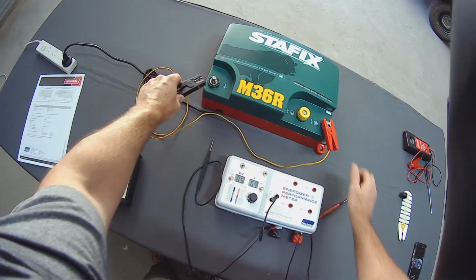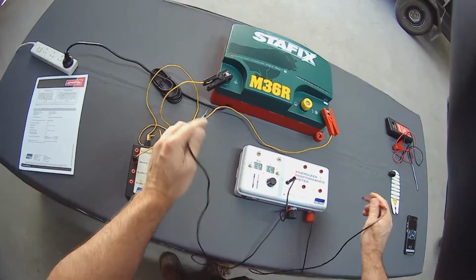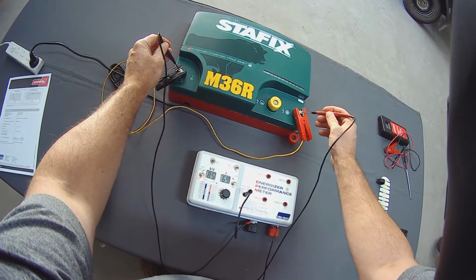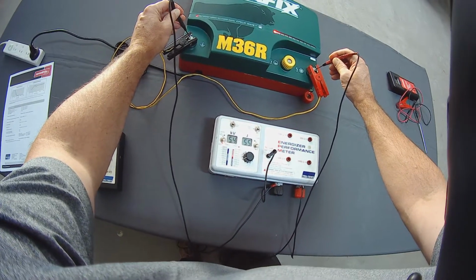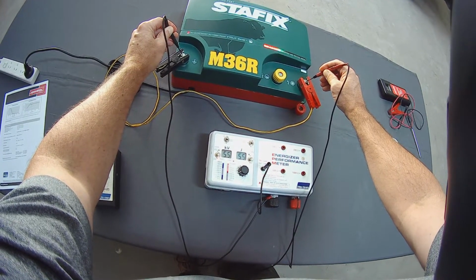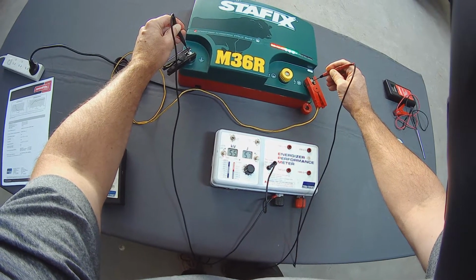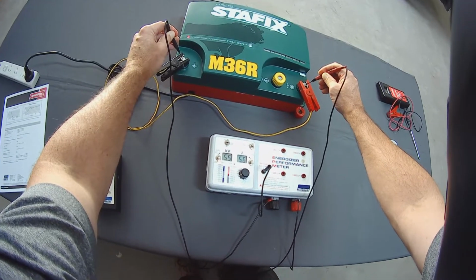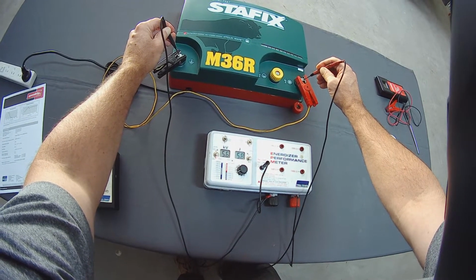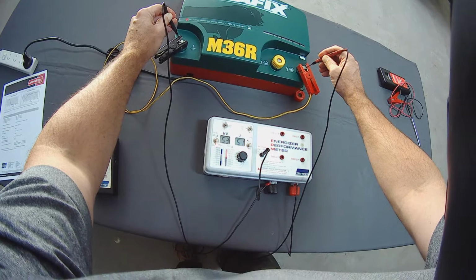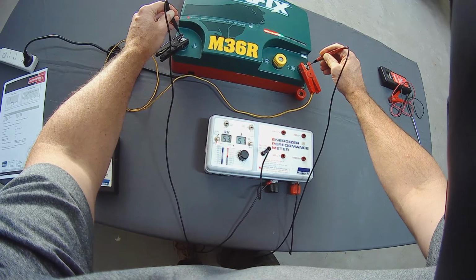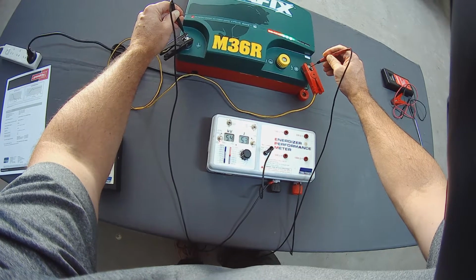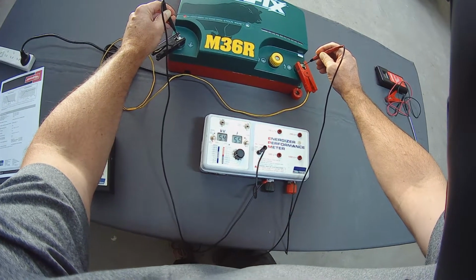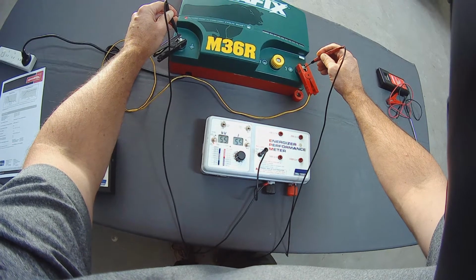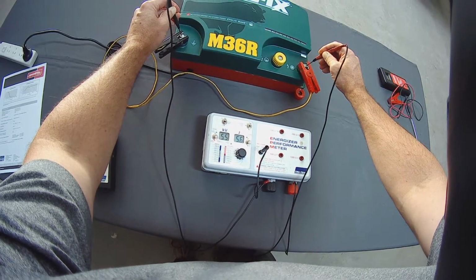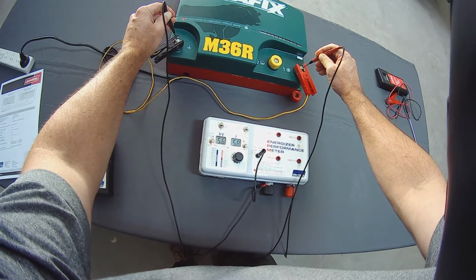We now apply this to the terminals, and we put our probes back on the terminals again. Now the Energiser will take a while to settle on a voltage and a joule output as the Energiser senses the extra load. It's working out how hard it needs to work to maintain that voltage. So as you can see, we're 5.1 joules with 5.4 kilovolts. Those joules are slowly starting to climb. 5.6, 5.7. It's working harder.